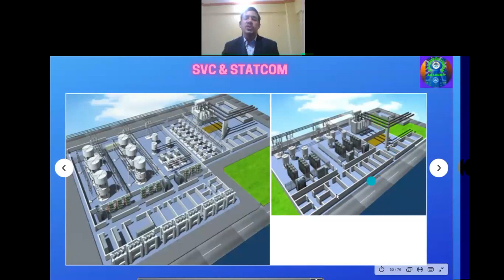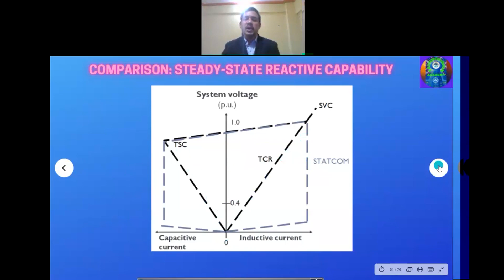Then this is the steady state reactive capability curve of STATCOM, static var compensator, SVC, TCR, TSC. In STATCOM, we can say that inductive current as well as capacitive current is possible, and we can maintain the voltage profile by injecting or absorbing reactive power into the system. We can actually control this voltage, or maintain the voltage profile of the system. So TSC has this characteristic, TCR has this characteristic.